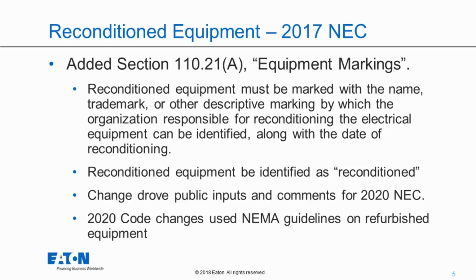What we see in the field very often is equipment being brought back up to operating condition, and because of the liability aspects, the original manufacturer does not want their company to be responsible for that reconditioning. So if you look at 110.21(A), it says that reconditioned equipment must be identified as reconditioned. It also talks about removal of listing marks, which we'll cover in the 2020 code changes in the next few slides. The 2017 change made them identify that we have to recondition, but it did not provide any guidance on what could or could not be reconditioned. That really drove a lot of public inputs and comments for the 2020 NEC.